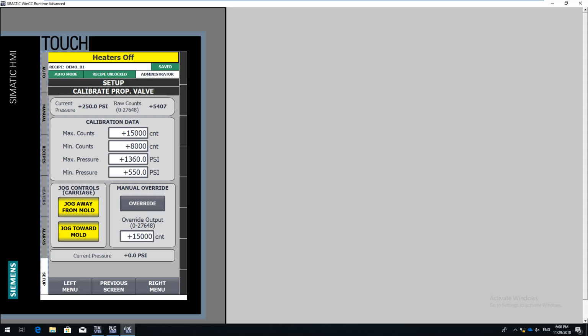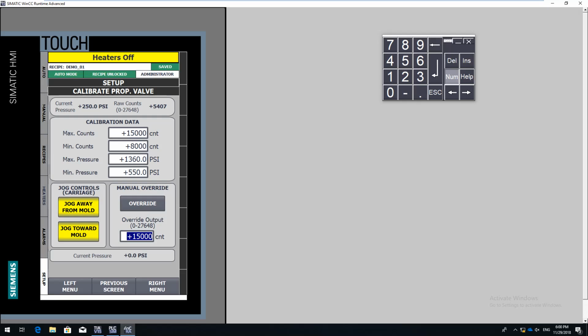Calibration data is the same, but what we do here, how we calibrate the system, kind of involves moving the carriage up and down in this override. So typically when we calibrate the proportional valve, one of the first things we have to do is set the pressure limit on the actual pump. To do that, what we'll do is we'll take our manual override and set it to the 27,648.